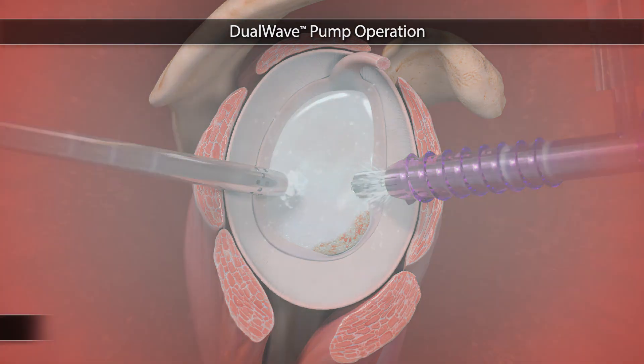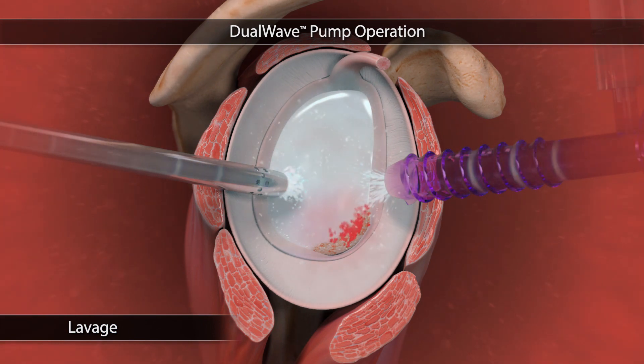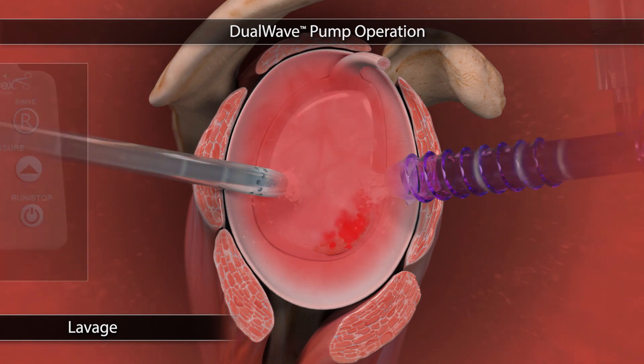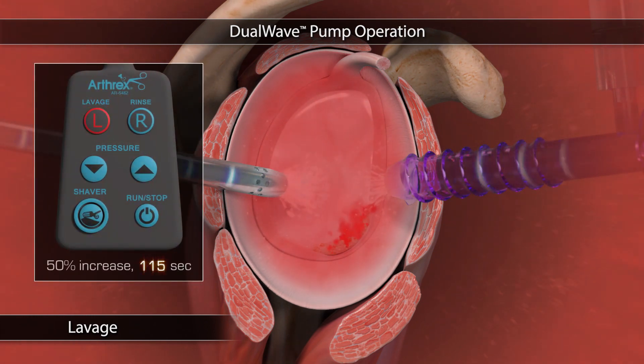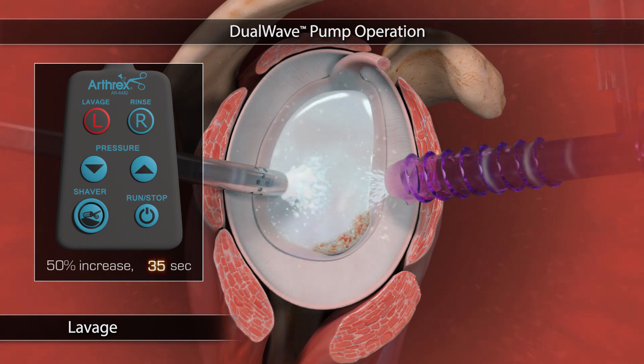Lavage is an important feature of the dual wave that produces a timed increase in pressure to control bleeding through tamponade. When bleeding occurs, the surgeon may press the lavage button to increase the pressure by 50% for two minutes. This allows hemostasis to be re-established and minimizes overall intra-articular pressure throughout the entire case.